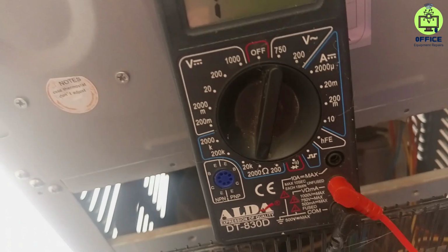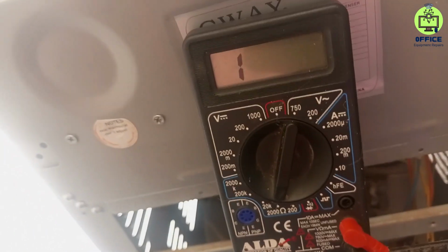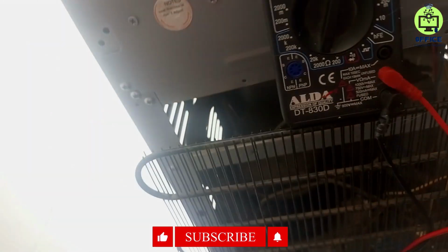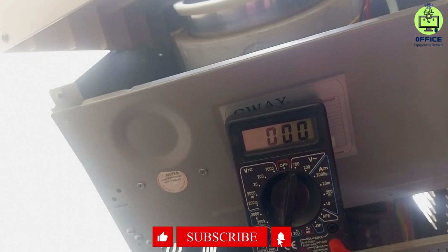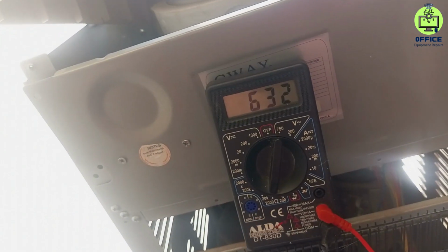So I'm going to get my multimeter and test for continuity. When I turn the sensor on and off, I'll check for continuity and see if there's a difference. If there's no difference when I turn it on versus off, then the thermal sensor is bad. This one is fine.